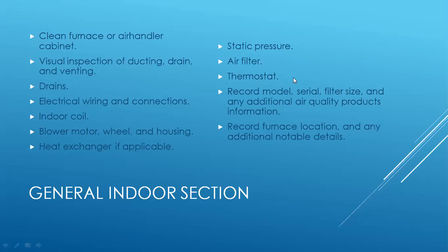Also, always check the thermostat. And it is a good idea, really, before you jump into the furnace section. I mentioned it a minute ago, but when you first get there, go to the thermostat, turn the fan on before you start checking air conditioning and stuff. Turn the fan to the on position, the blower motor should come on. If the motor doesn't come on, make a mental note of that. Tell the customer, hey, the fan's not coming on. Let me dig into this and see what's going on. Because otherwise, it was working just fine before you got here.